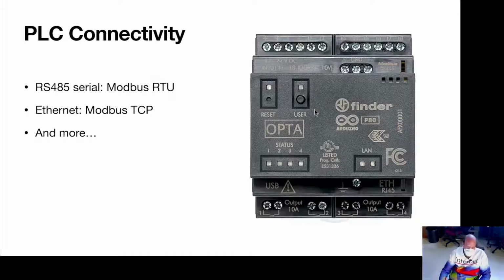Built on top of that, on each of those, is a protocol called Modbus. So Modbus RTU is the Modbus protocol running on top of RS485 serial. Modbus TCP is the protocol running on top of Ethernet and IP.